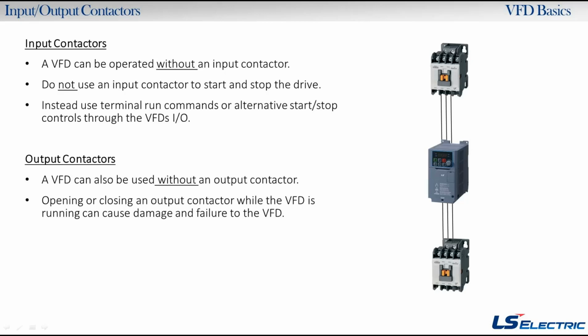And then if it blows out that resistor, again, the drive's just not going to work. Output contactors are a similar story. You don't need output contactors, because you could just stop the drive with your deceleration time and whatever time you need. And then you just drop your run command out, and then the drive's going to stop. If you really want to use output contactors, that's okay, but we would recommend somehow interlocking it with the drive's run command, so the contactor doesn't go open until the drive is stopped.